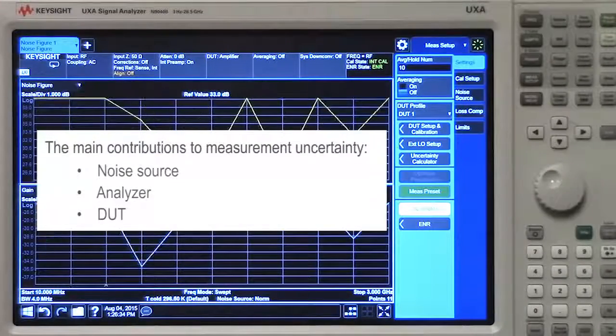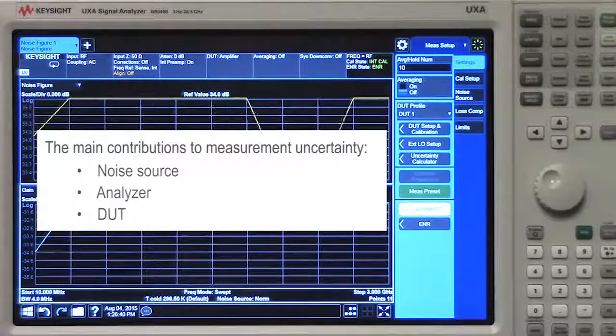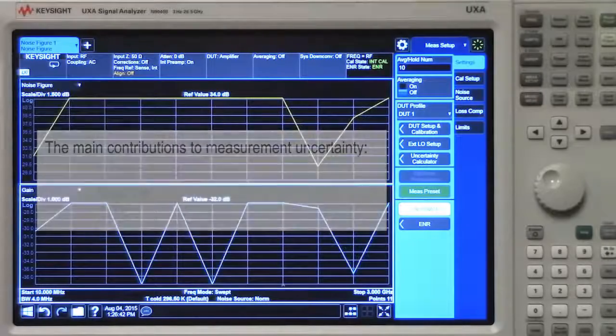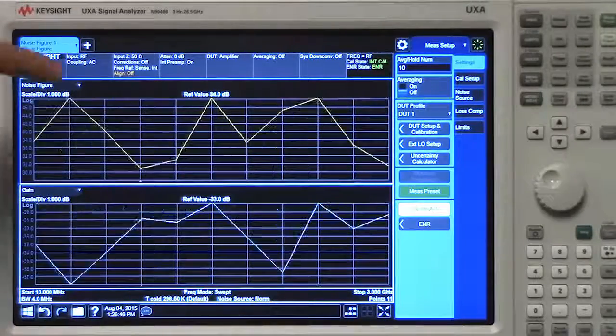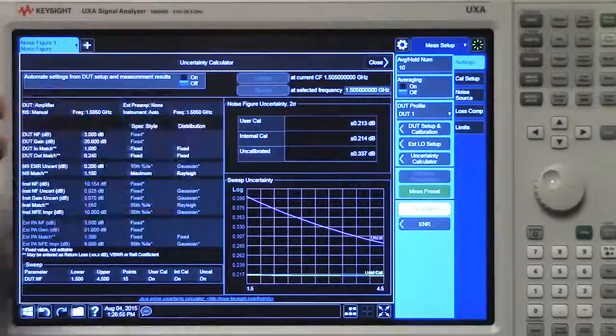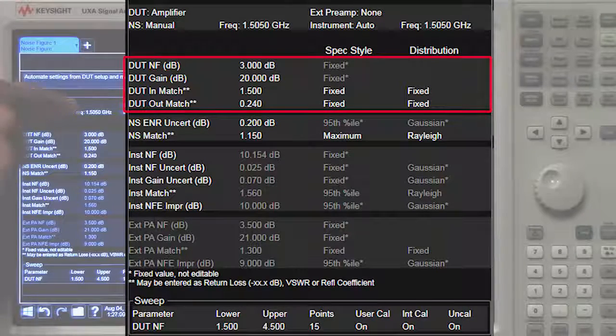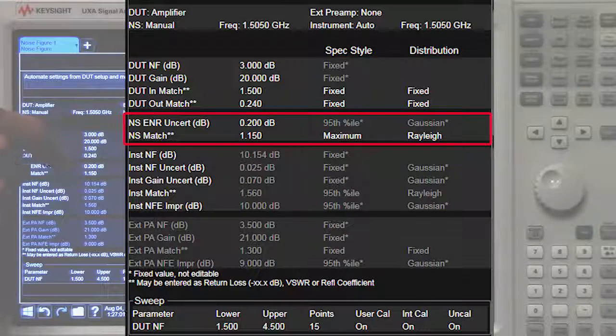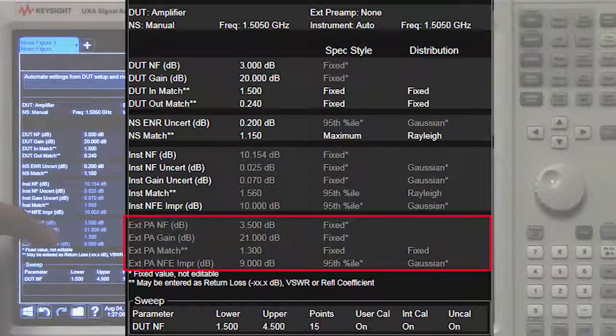We need information about all three of these in order to get reliable uncertainty readings. Let's see how connecting our smart devices can automatically populate the necessary fields and save us some valuable time. Let's go to the measurement setup menu panel and press uncertainty calculator. Right now, we have fields for the device, the noise source, for the analyzer, and an optional external preamp.